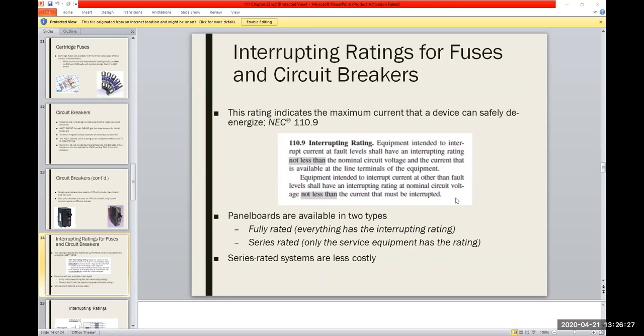So, you can look up, they do have a rating, right, like NEC 110, and this is the very beginning of the book. We didn't even read this, right? It's equipment intended to interrupt current at fault levels, and it shall have an interrupt rating not less than the nominal circuit voltage and the current that is available at the line terminals of the equipment.